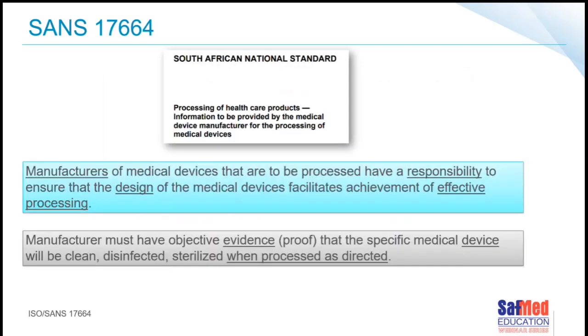So the manufacturer of a medical device has a responsibility to ensure that the design of the device itself actually facilitates the achievement of effective processing. So they've got to make sure that it's designed in such a way that you can clean it, that you can reprocess it, that you can sterilize it. The manufacturer must have this objective evidence, so proof that if you follow their steps as they have described them, the instrument will in fact be cleaned, disinfected and sterilized if you follow the instructions for use.